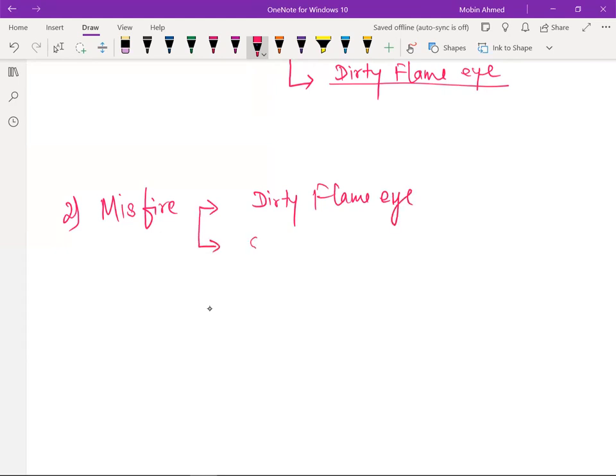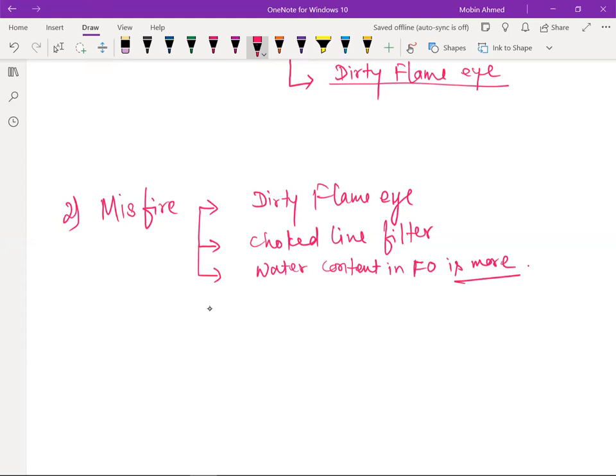Second is a choked line filter. There is a line filter in this one. This is one cause, or water content in the FO. Again, Fujairah fuel oil is very, very problematic. If the water content in the FO is more, or the purifier is not working or has some issue, then you are going to have a misfire. Meaning just ignition will be there, the flame will be there, and thereafter no flame after 10 seconds.